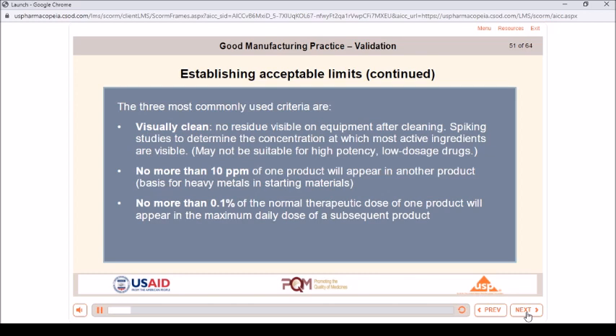Establishing acceptable limits. Continued. The three most commonly used criteria are visually clean, no residue visible on equipment after cleaning, spiking studies to determine the concentration at which most active ingredients are visible, may not be suitable for high potency, low dosage drugs. No more than 10 ppm of one product will appear in another product, basis for heavy metals in starting materials. No more than 0.1% of the normal therapeutic dose of one product will appear in the maximum daily dose of a subsequent product.